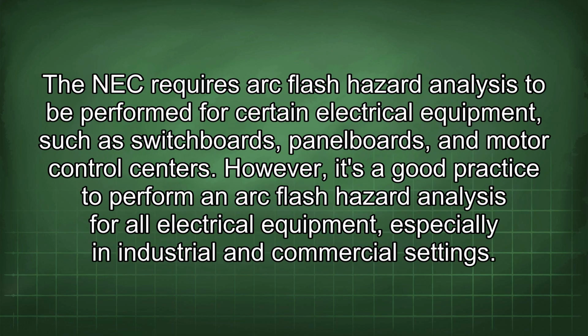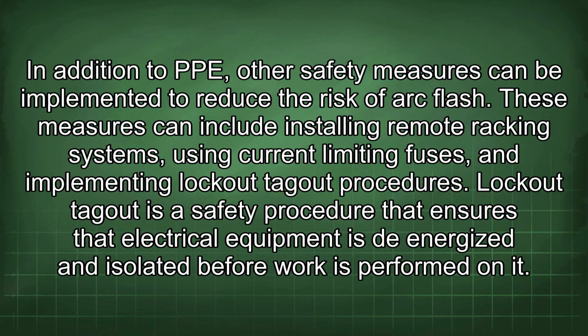The NEC requires arc flash hazard analysis to be performed for certain electrical equipment such as switchboards, panel boards, and motor control centers. However, it's a good practice to perform an arc flash hazard analysis for all electrical equipment, especially in industrial and commercial settings. In addition to PPE, other safety measures can be implemented to reduce the risk of arc flash. These measures can include installing remote racking systems, using current-limiting fuses, and implementing lockout-tagout procedures.